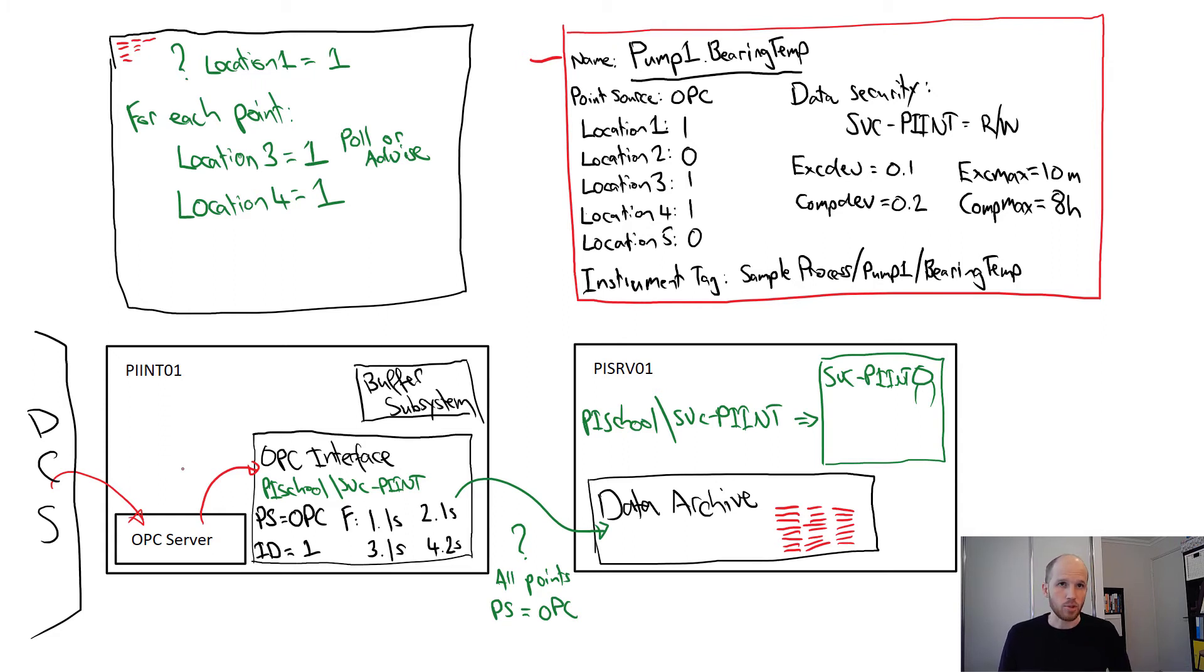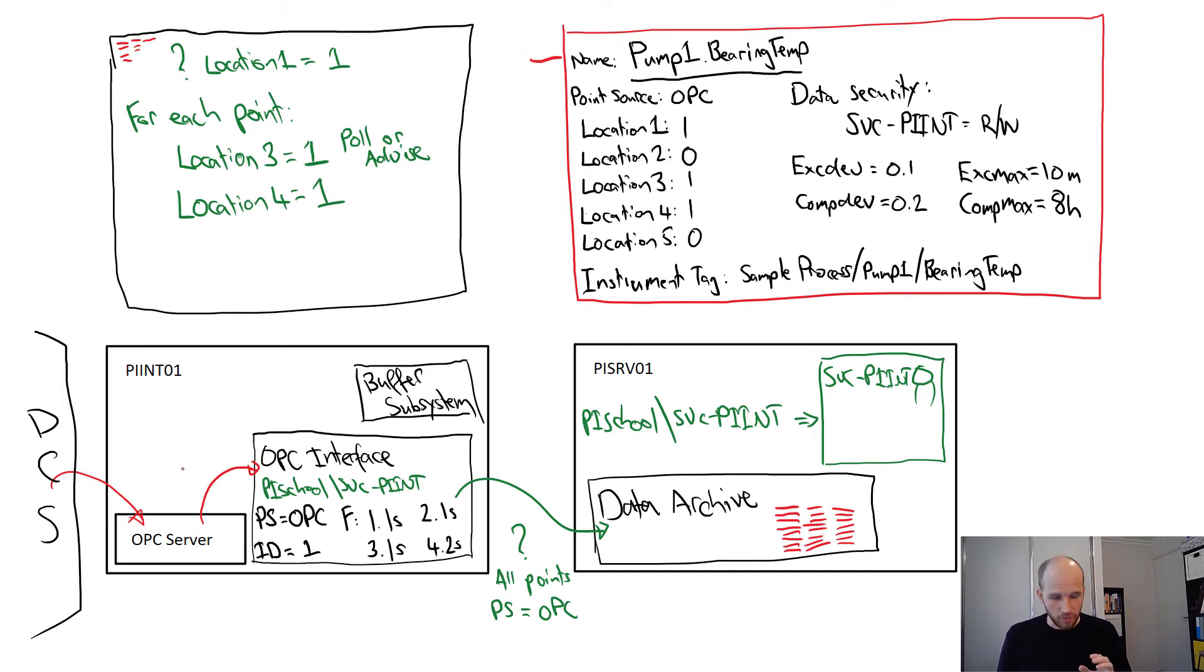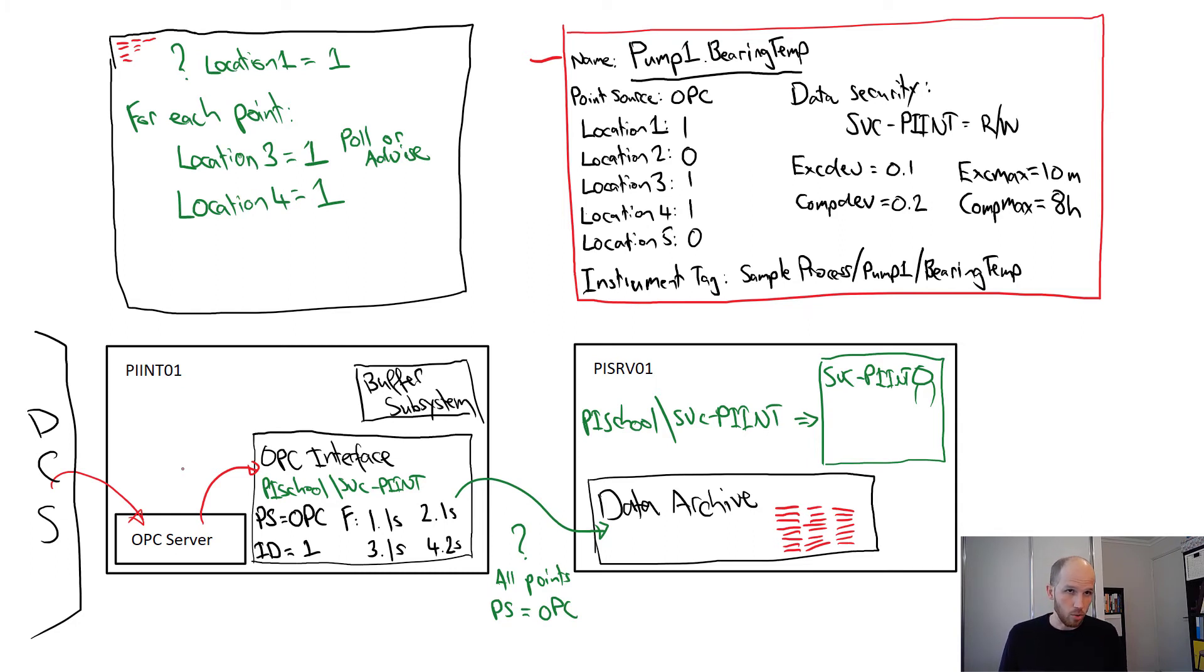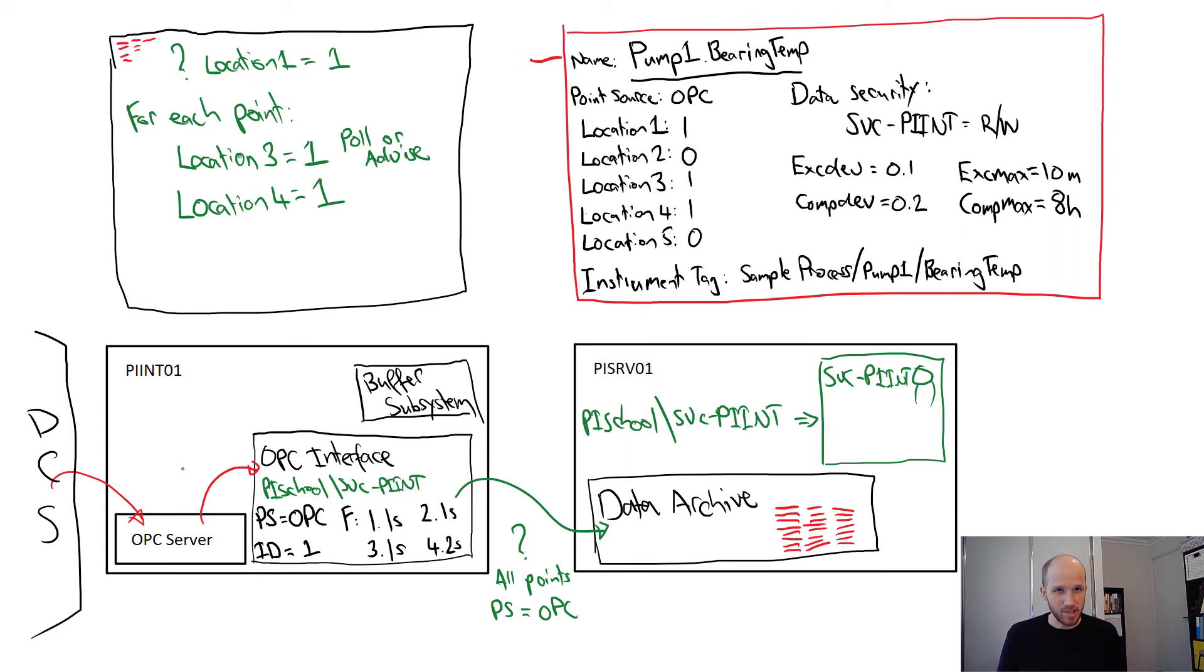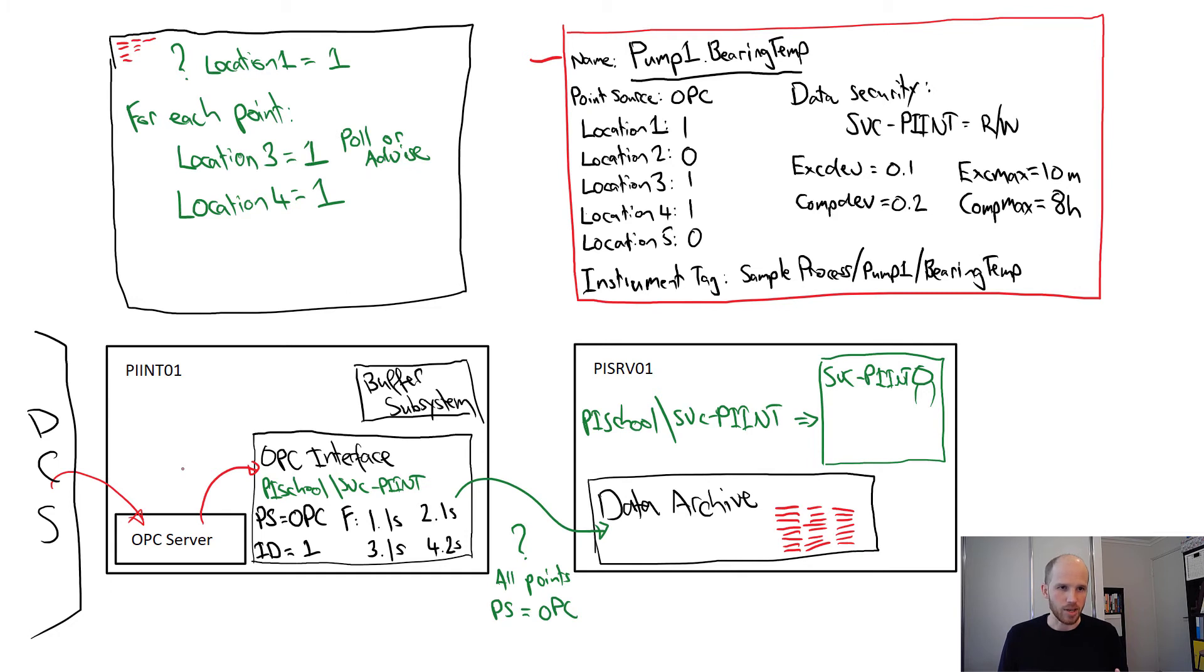The exception to that is the first scan class. If tags have a location 4 equal to 1, they must be advise tags, so the location 3 also must be 1, and they're automatically allocated to groups on the server. In most cases, this will be just fine. If you're having trouble with the OPC server, you can check the documentation for more details on how you can split these up.